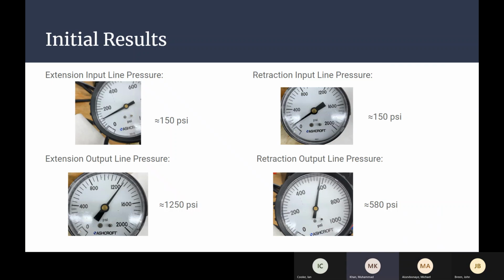These pictures show the pressure in our hydraulic lines for a full extension and then full retraction of our actuator. When we constrain our linkage and increase the friction between bearings, we see a slight increase in the necessary pressure needed to operate the actuator. This can be seen as an impulse by the gauge. As we introduce our digital transducer, we will expect to see more clear-cut values that can aid us in determining a relationship between bearing failure and pressure traces.